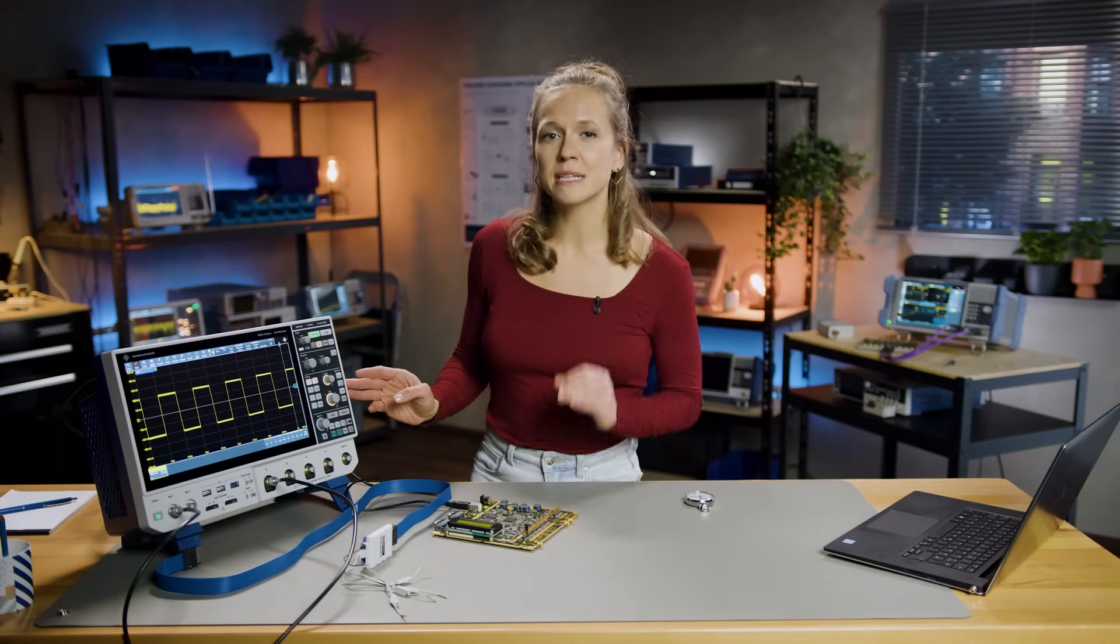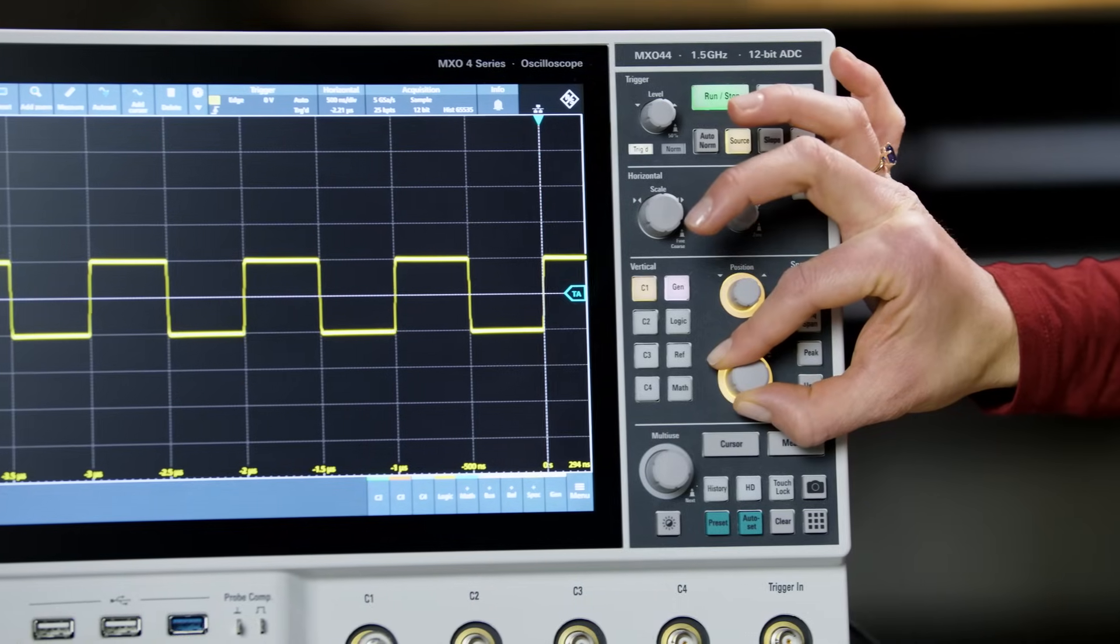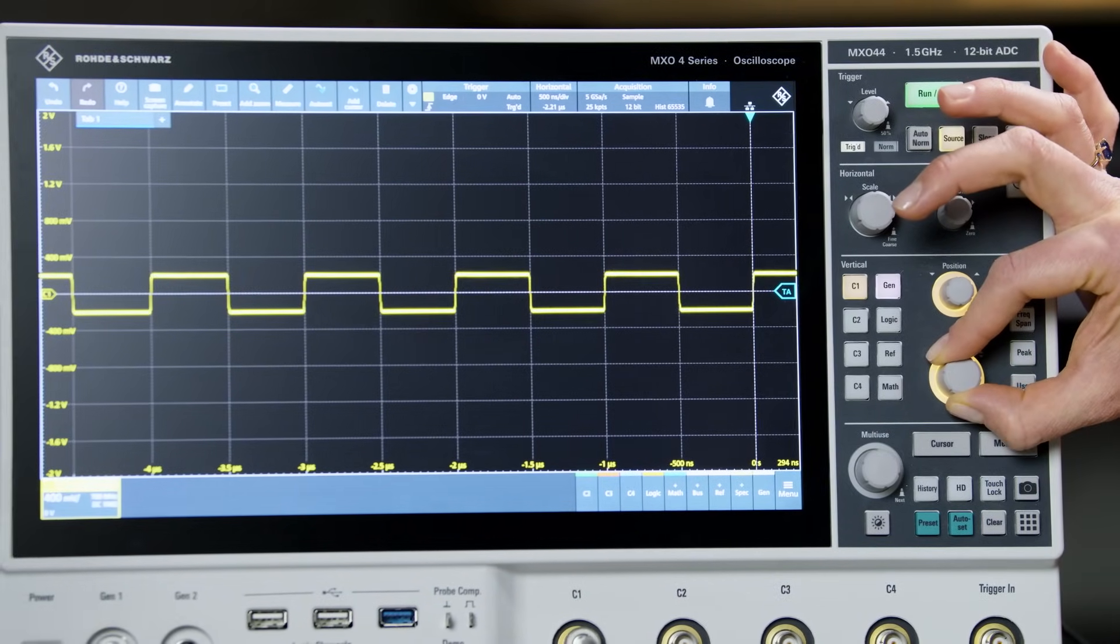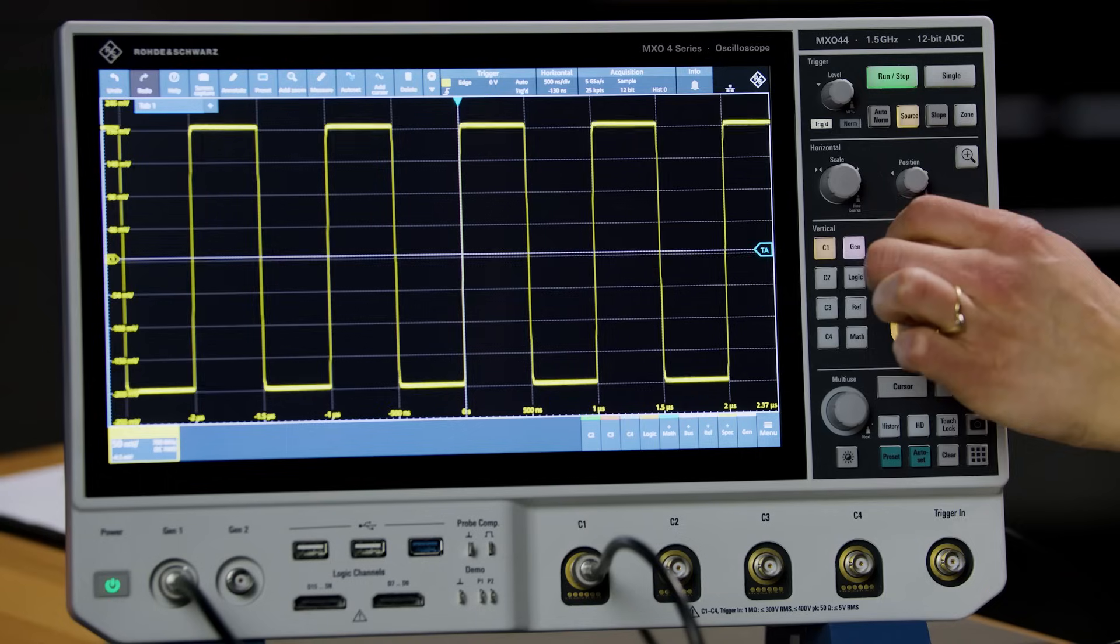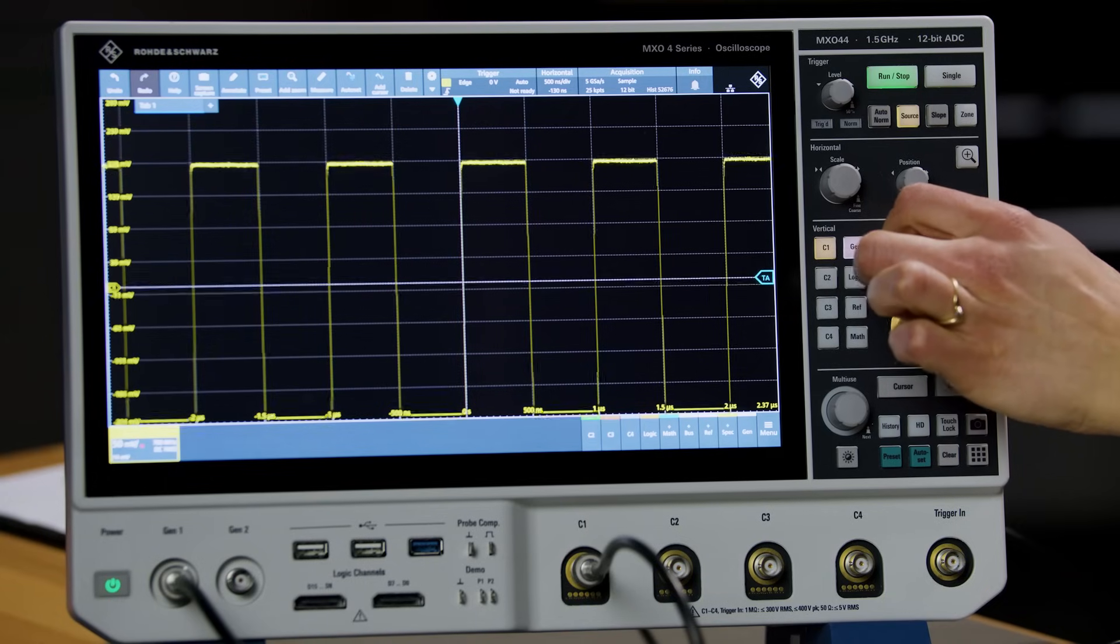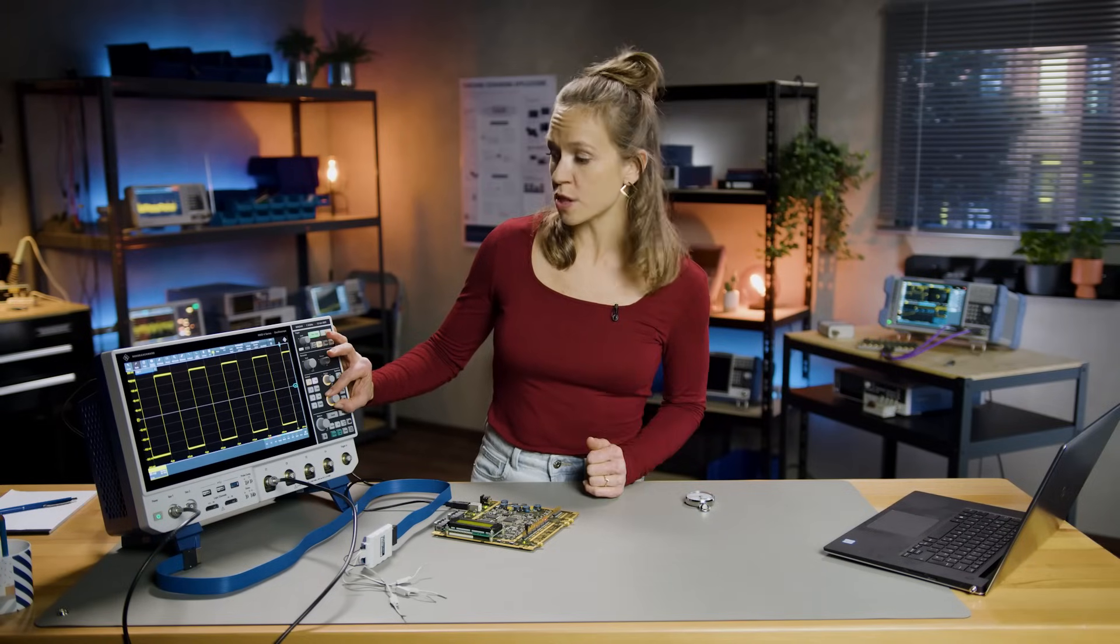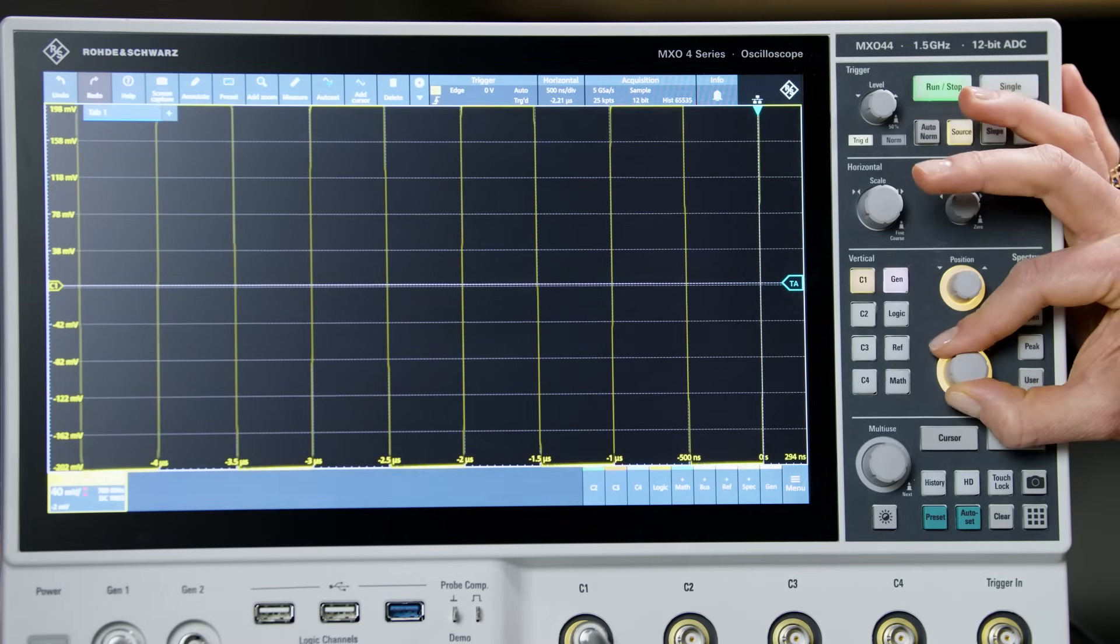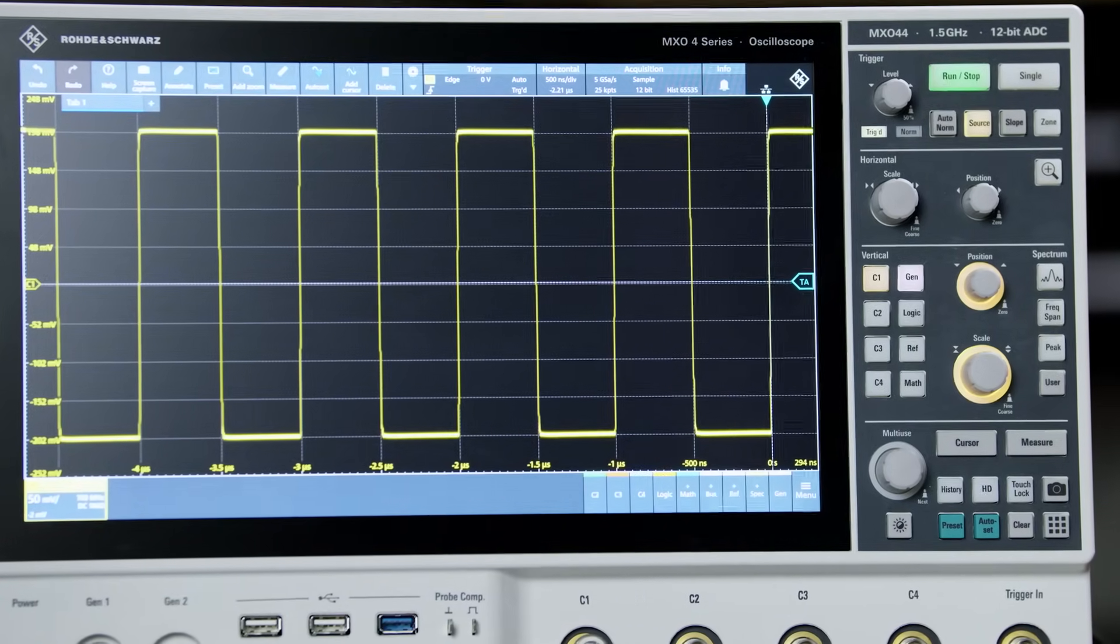When configuring the vertical system, it is important to remember to maximize the display of the waveform on the screen. Look what happens when I adjust the voltage per div setting. The higher the voltage per div is selected, the smaller the representation of the waveform. Use the position knob to move the waveform up and down on the screen. To make best use of the scope, you need to position the highest and lowest points on the waveform as close as possible to the top and the bottom of the screen, without clipping the waveform. With maximum vertical scaling, it is easier to detect small details or defects in a waveform.